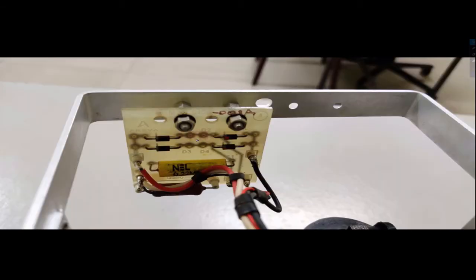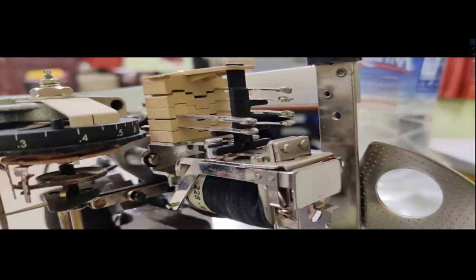Now, as I mentioned, the trip signal requires DC power, so this is a rectifier, and using this rectifier, the AC is converted to DC, and this DC is supplied to the tripping coil. Once the tripping circuit is closed by the disk or the arrangement by the disk, the DC power from that rectifier will flow to the tripping coil, and the tripping coil generates the trip signal. Here you see this is a solenoid type relay. DC power is required for generating the uniform or unidirectional force.